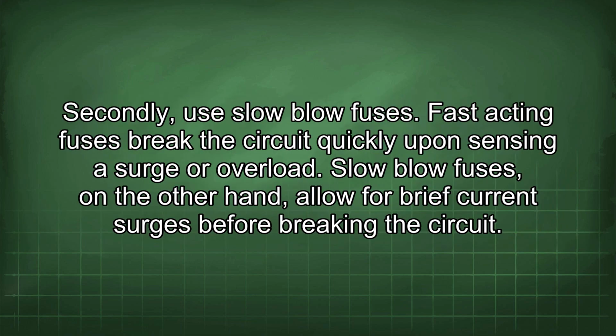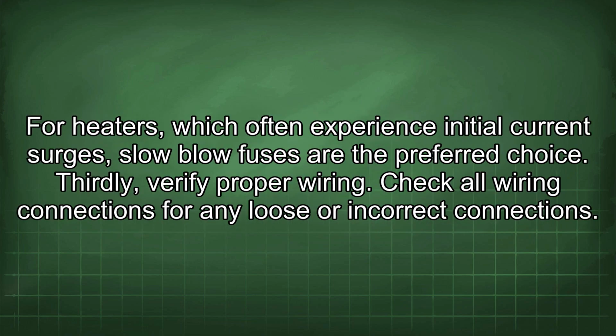Secondly, use slow blow fuses. Fast-acting fuses break the circuit quickly upon sensing a surge or overload. Slow-blow fuses, on the other hand, allow for brief current surges before breaking the circuit. For heaters, which often experience initial current surges, slow-blow fuses are the preferred choice.